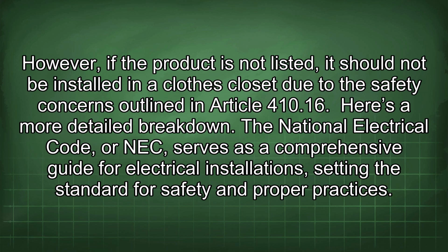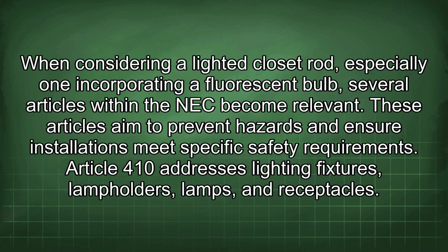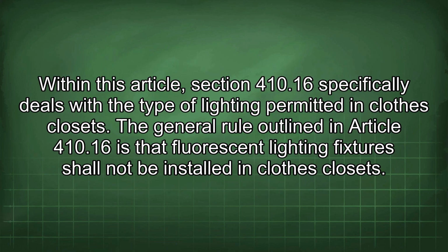The National Electrical Code, or NEC, serves as a comprehensive guide for electrical installations, setting the standard for safety and proper practices. When considering a lighted closet rod, especially one incorporating a fluorescent bulb, several articles within the NEC become relevant. These articles aim to prevent hazards and ensure installations meet specific safety requirements. Article 410 addresses lighting fixtures, lamp holders, lamps, and receptacles. Within this article, Section 410.16 specifically deals with the type of lighting permitted in clothes closets.